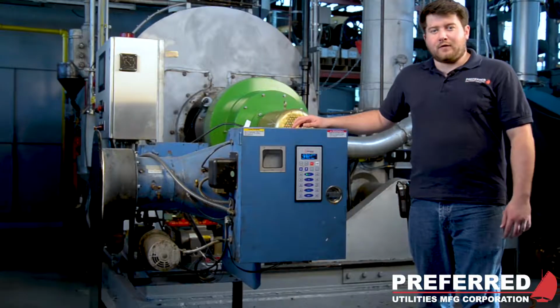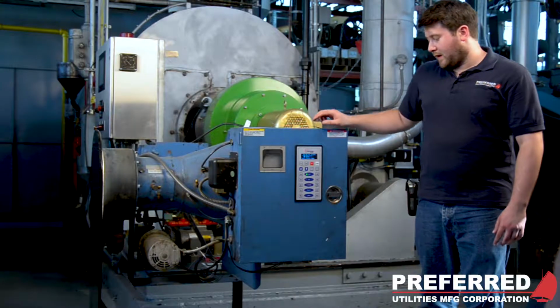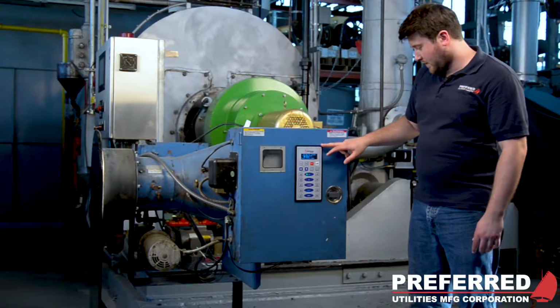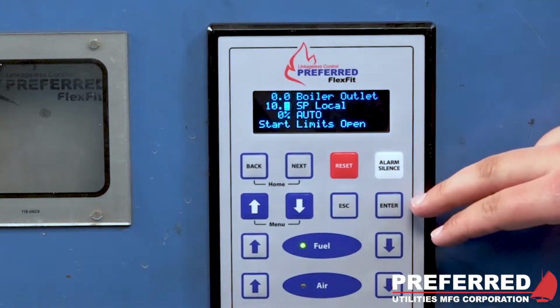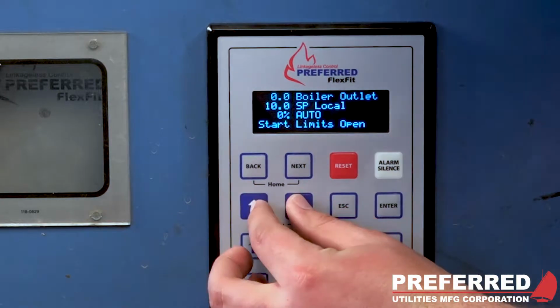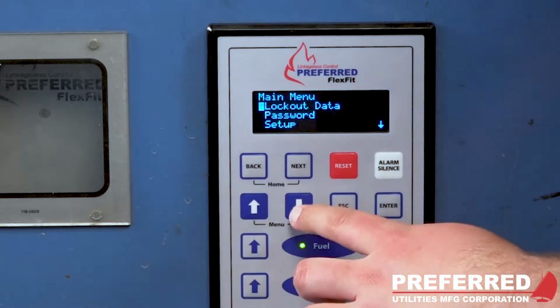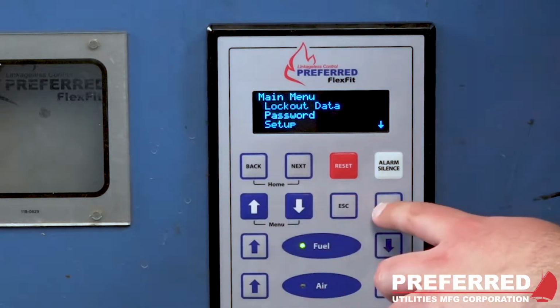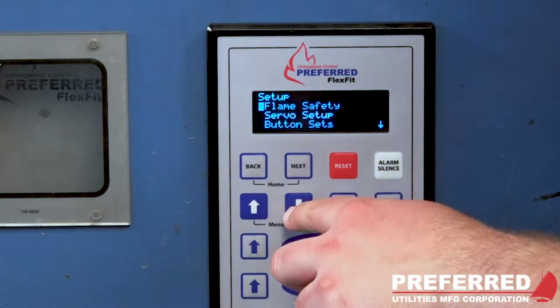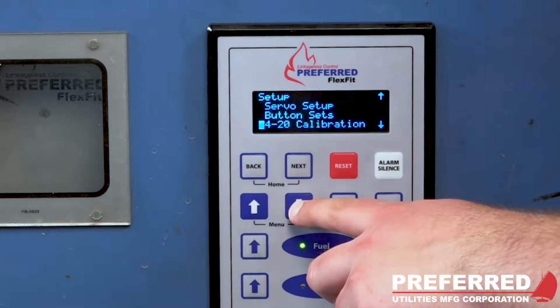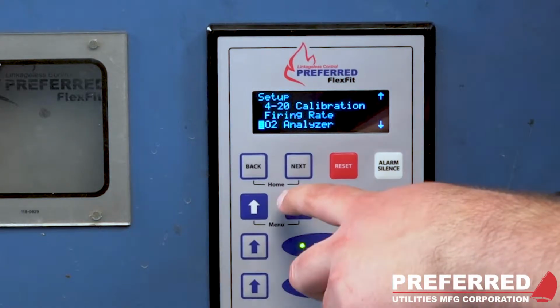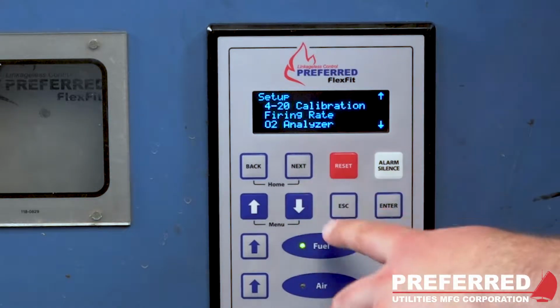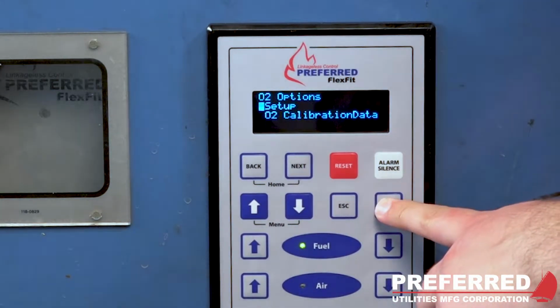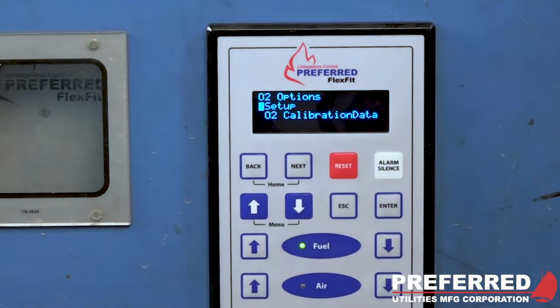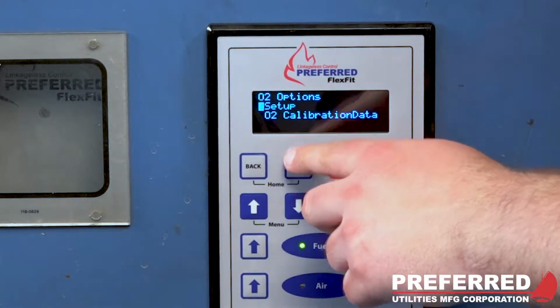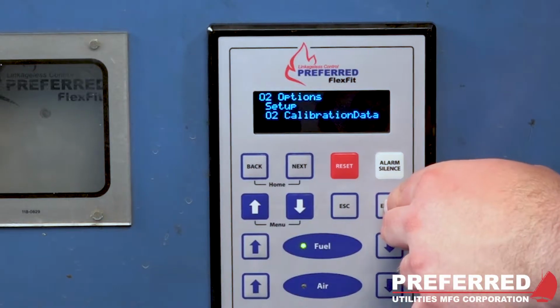So now that we have the O2 sensor wired in, we can go ahead and set it up on the LCD keypad. So first, you want to go into Menu, scroll down to Setup, scroll down again all the way to O2 Analyzer. Alright, now you have two options, Setup and O2 Calibration Data. We'll start with the Setup option.